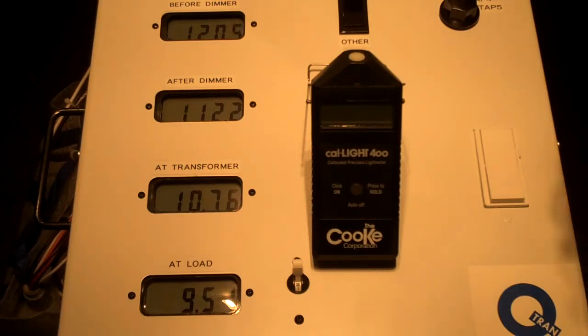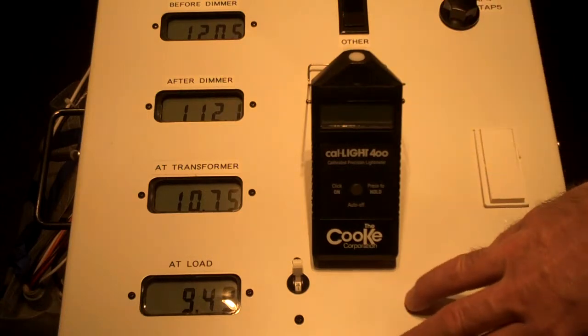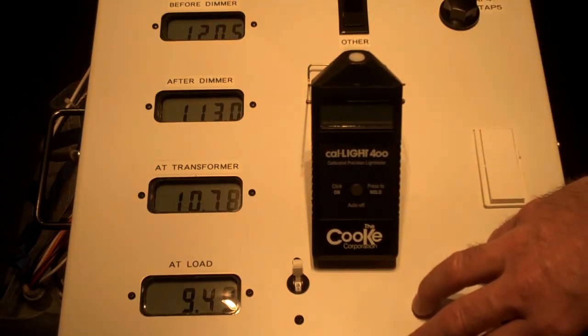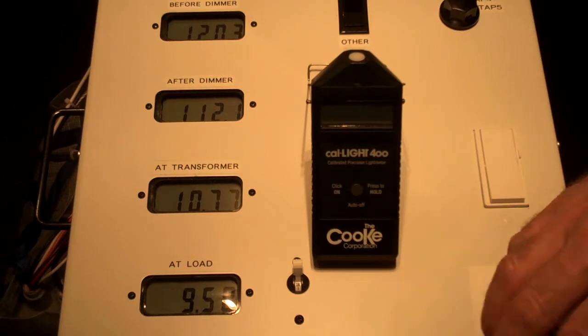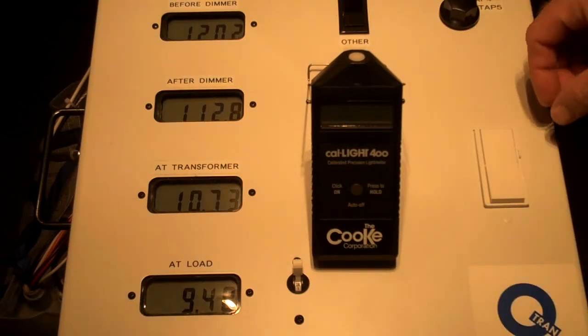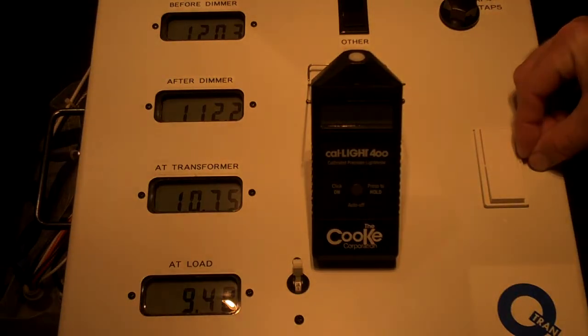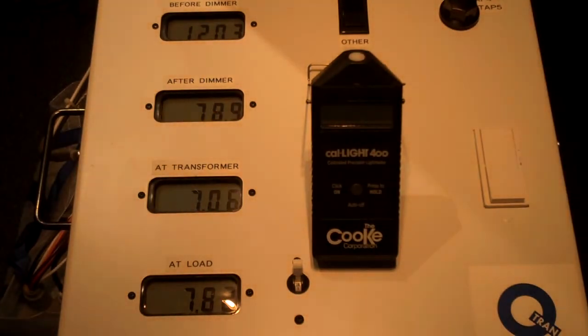In addition to that, this demonstration kit shows the audible difference between our transformers and other transformers. So in here we have a standard stack laminated or EI transformer that most other manufacturers use, and then we have one of our toroidals. I don't know if you'll be able to pick up the sound difference, but most transformers make an audible noise, especially when you dim them. As you dim, you begin to turn the lights on and off through the triac inside the dimmer, and that puts the transformer under stress and will cause it to make a buzzing or a humming noise.